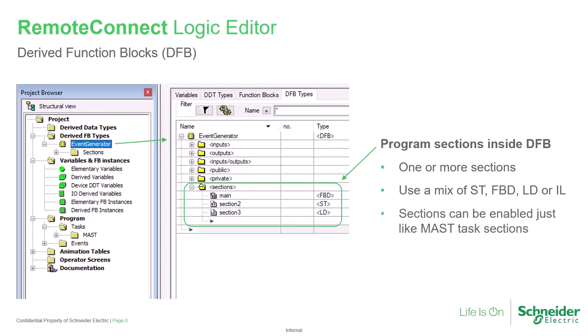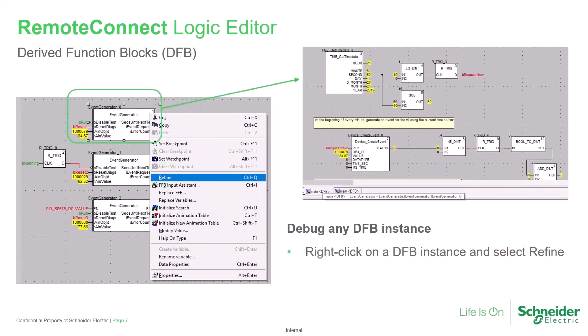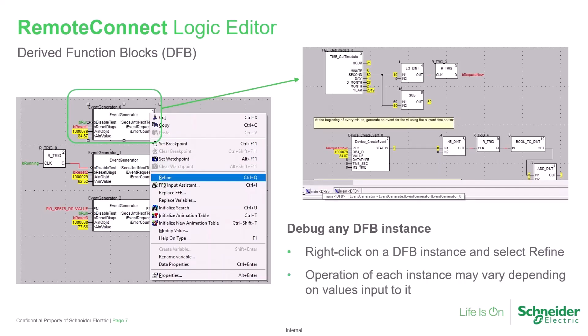These sections may be enabled or disabled with a control object, just as main program or MAST logic sections can be. And as a very helpful diagnostic tool, it's possible to debug any DFB instance while connected to the RTU. Just right-click on the DFB instance and select the Refine option. This can be very helpful as the operation of any DFB may vary from others of the same type, depending on the values fed into it.